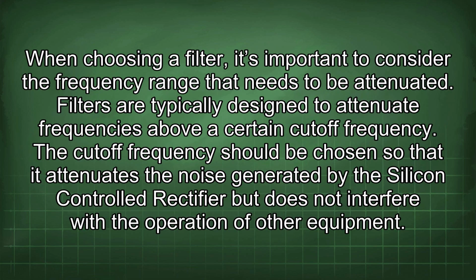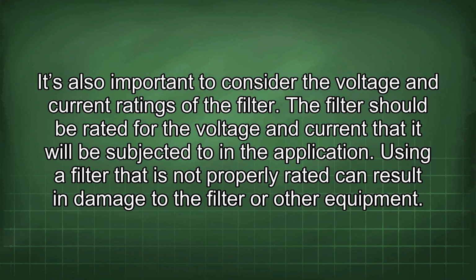When choosing a filter, it's important to consider the frequency range that needs to be attenuated. Filters are typically designed to attenuate frequencies above a certain cutoff frequency. The cutoff frequency should be chosen so that it attenuates the noise generated by the silicon-controlled rectifier but does not interfere with the operation of other equipment. It's also important to consider the voltage and current ratings of the filter. The filter should be rated for the voltage and current that it will be subjected to in the application. Using a filter that is not properly rated can result in damage to the filter or other equipment.